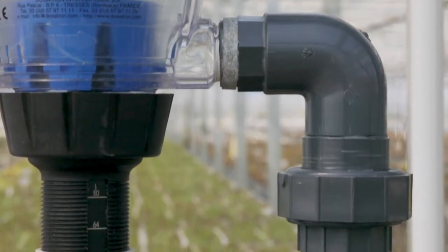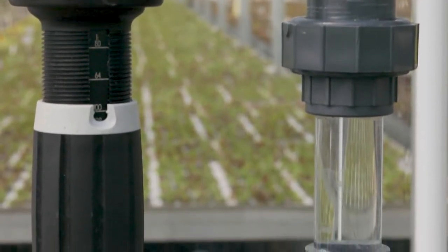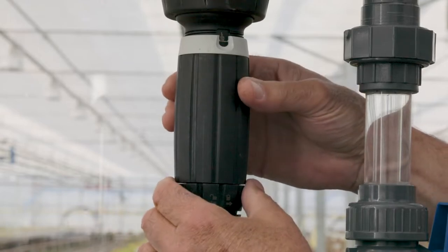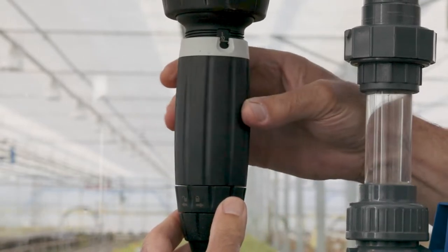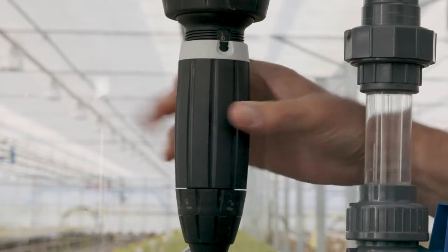The dilution of the concentrated feed is set by these marks on the actual throat of this inlet pipe. One in fifty, one in one hundred and further down is a one in two hundred dilution. So that's two percent, one percent and half a percent dilution.